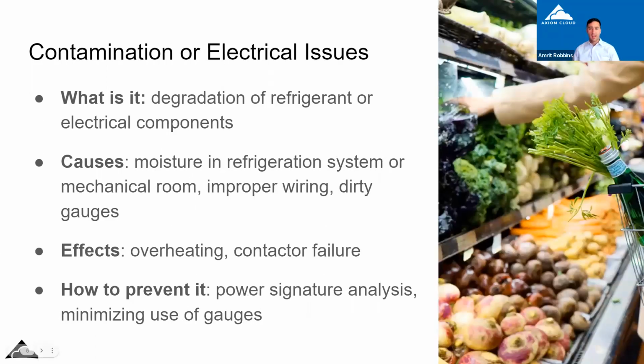All right, our last category is contamination or electrical issues. This is degradation of refrigerant or electrical components. One thing I like to think about, if you zoom out and think about this topic as a whole, is that you have this compressor sitting in the center of your diagram. Then there are all kinds of inputs and outputs, and each one of those is a way to potentially kill the compressor. If you put in dirty refrigerant, that can kill the compressor. If you put in dirty electrical current, that can kill the compressor. Or if the electronics are malfunctioning and sending weird electrical waveforms into the compressor, that's bad too.